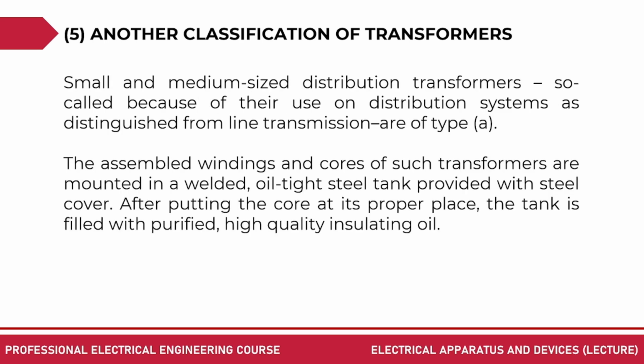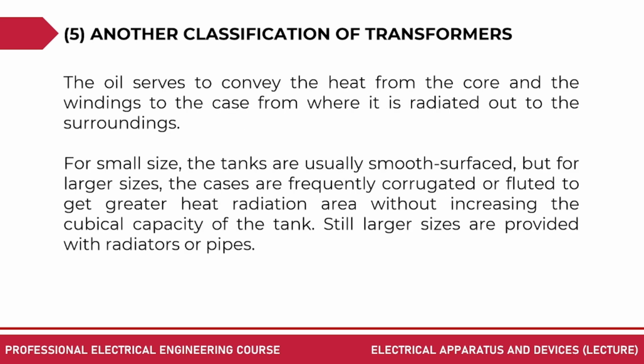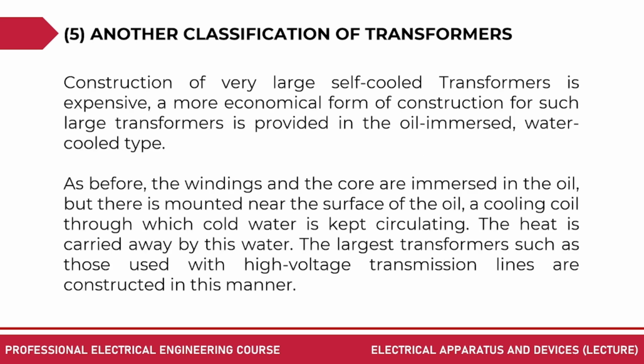The assembled windings and cores of such transformers are mounted in a welded, oil-tight steel tank provided with steel cover. After putting the core at its proper place, the tank is filled with purified, high-quality insulating oil. The oil serves to convey the heat from the core and the windings to the case from where it is radiated out to the surroundings. For small size, the tanks are usually smooth surfaced, but for larger sizes, the cases are frequently corrugated or fluted to get greater heat radiation area without increasing the cubical capacity of the tank. Still larger sizes are provided with radiators or pipes. Construction of very large self-cooled transformers is expensive.